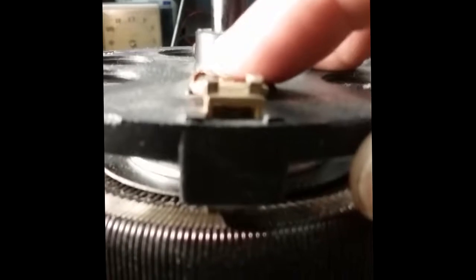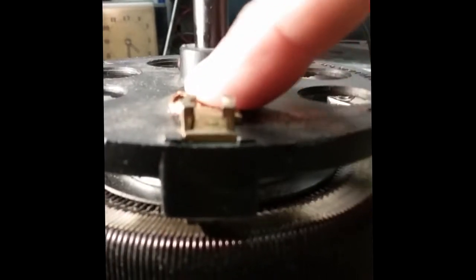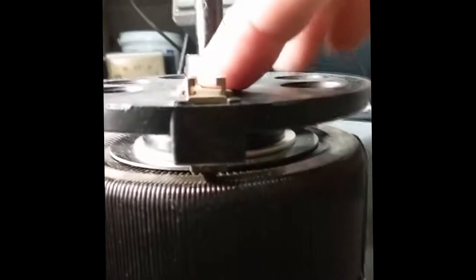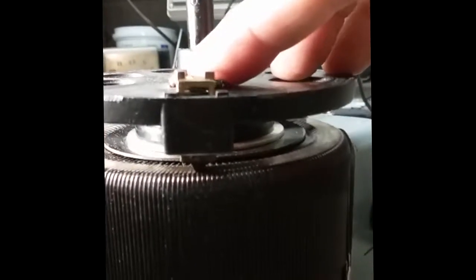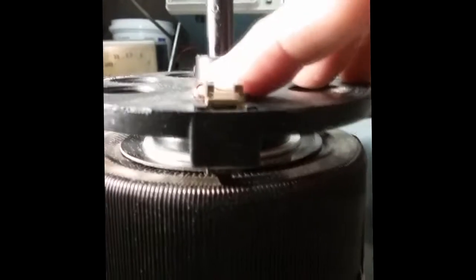So I adjusted that by adjusting the height of the gear, the pulley here, so that when I tighten the screw, you see it's at worse shape there, I tighten the screw, and see it gives you plenty of contact on that, down on the bottom down there. Plenty of pressure to hold that contact against the coil. That was, like I said, one of the parts that wears out the most on these, is that contact pressure. It drops away as the contact is worn down. But this contact's in great shape.